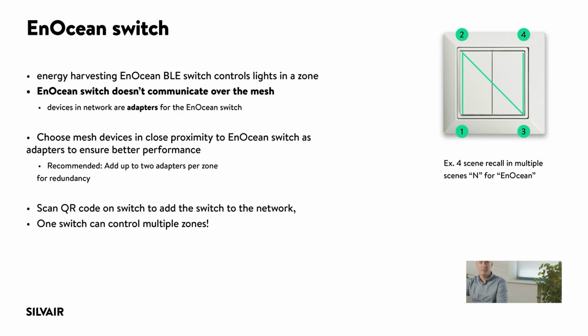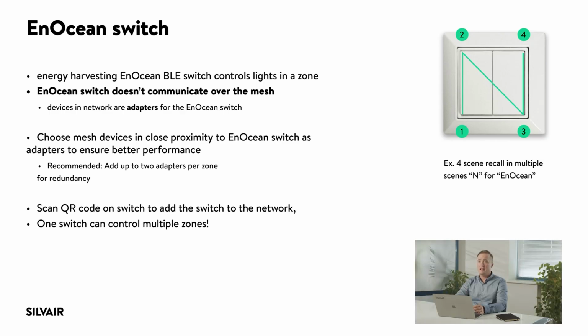Energy harvesting EnOcean devices are extremely convenient for manual control or scene selection. However, since they cannot directly communicate over the mesh, they require devices in the network to act as EnOcean adapters to forward their traffic.